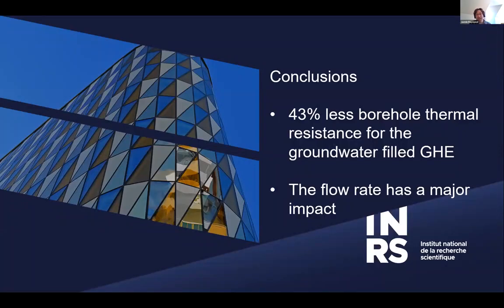So this concludes my talk. The take-home message is that geothermal heat pump systems can be improved and better designed by minimizing the borehole thermal resistance. There are different alternatives for doing this, and groundwater-filled boreholes are one of the interesting options to look at, although they're not very common right now in the industry. But I believe it's something that should be more and more used, especially for systems that are designed for cooling purposes, which I guess would be the case for your system in Colombia. And one of the keys in designing those systems is to look at the flow rate, which has an important impact on the borehole thermal resistance. Thank you. I guess this concludes my talk.